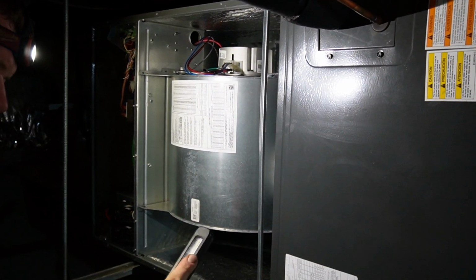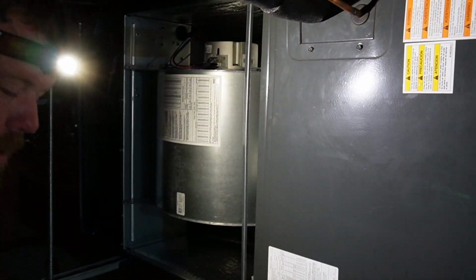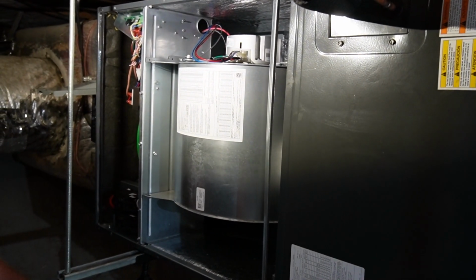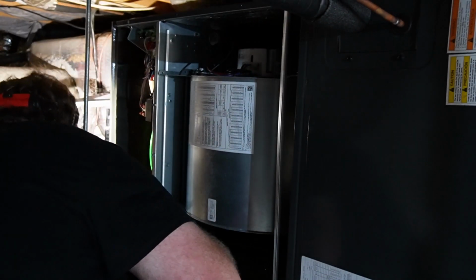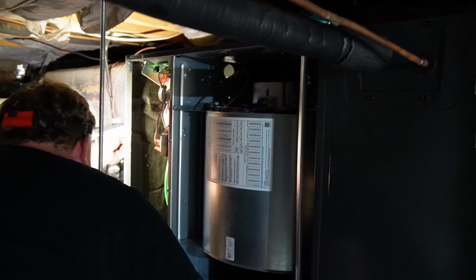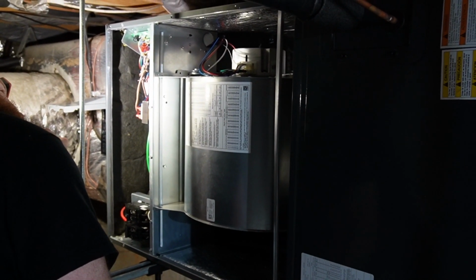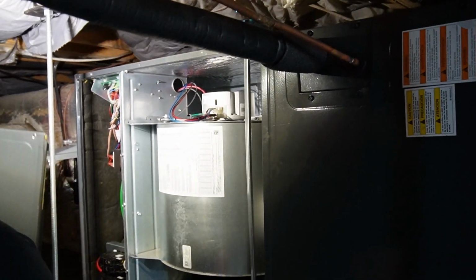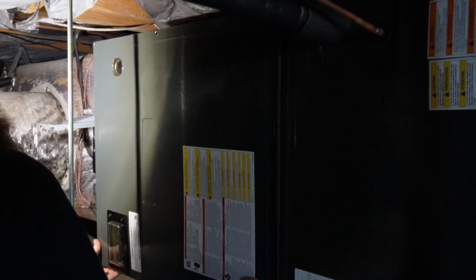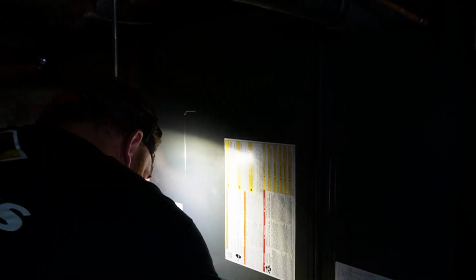All right, so we're closing in on firing the system up. 30 minutes into days of trying. Yeah, after the guy gave up, we are applying power. We're gonna test cooling. What's crazy is this unit was installed last year, and this will be the first time it's ever seen cooling. We are June 2nd, 83 degrees outside, and this unit ran all last year, winter season, without heat strips. So I'm sure that was a marathon for the outdoor unit, but we'll fire it up and do some tests.